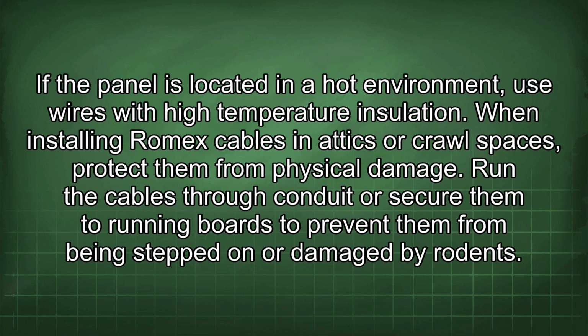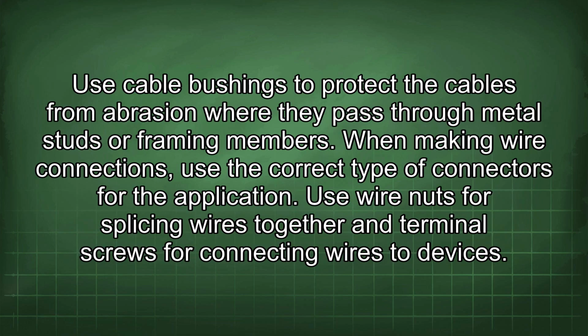When installing Romex cables in attics or crawl spaces, protect them from physical damage. Run the cables through conduit or secure them to running boards to prevent them from being stepped on or damaged by rodents. Use cable bushings to protect the cables from abrasion where they pass through metal studs or framing members.